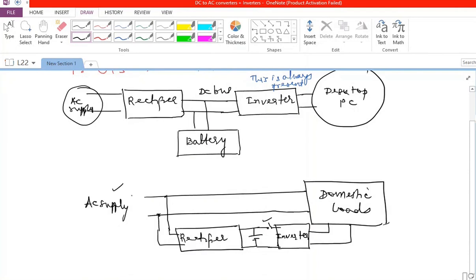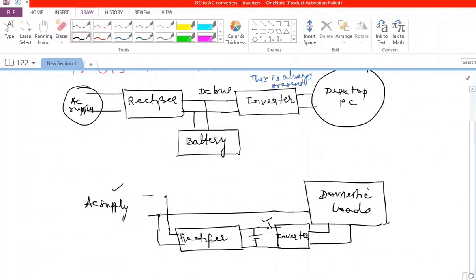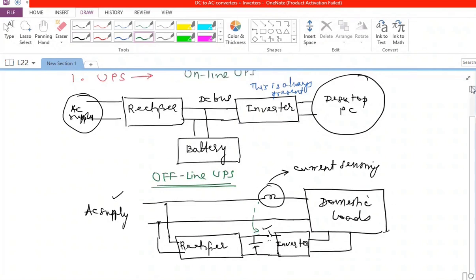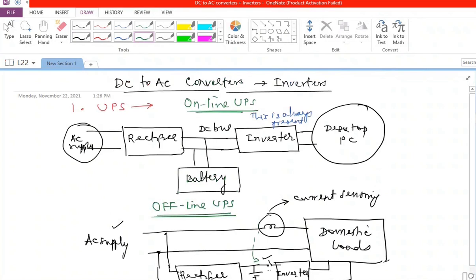When AC supply fails, there is a small glitch for a fraction of a second because the switch takes some time to close. Current is sensed from the AC side; when that current goes to zero because the supply has failed, the switch closes and the domestic load is supplied by the already-charged battery. This is generally known as an offline UPS because the inverter is not always in the circuit.